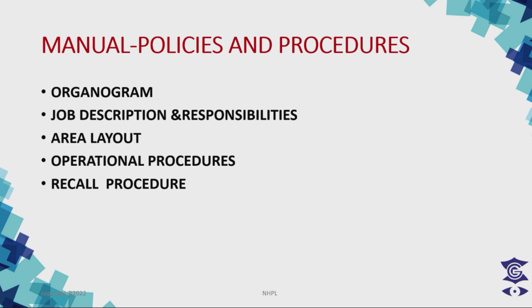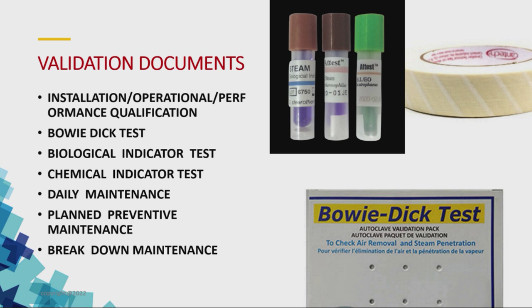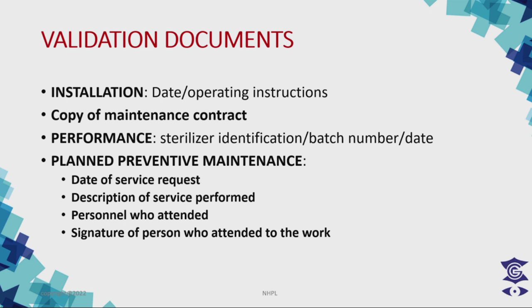Coming to the validation documents, there will be the installation, operational, and performance qualification. These have to be maintained, and also the indicators that are used, and the daily maintenance, planned preventive maintenance, and breakdown maintenance. So all these records come under validation documents. In the installation, there will be the date and operating instructions, and a copy of the maintenance contract. Coming to the performance, sterilizer identification, batch number, and date all have to be in the record. And in case of planned preventive maintenance, the date of service request, description of service performed, personnel who attended, and the signature of the person who attended to the work all have to be documented.